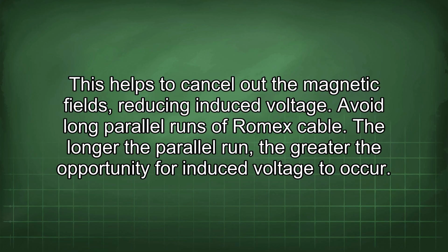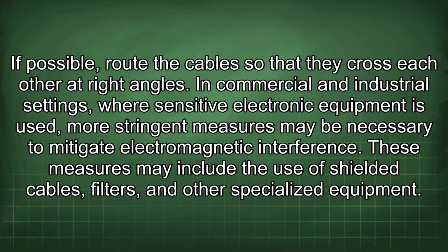Avoid long parallel runs of Romex cable. The longer the parallel run, the greater the opportunity for induced voltage to occur. If possible, route the cables so that they cross each other at right angles.